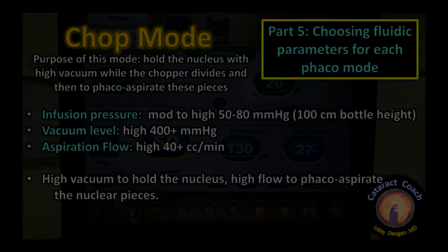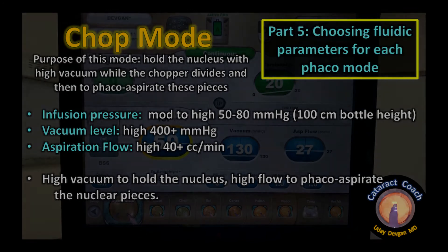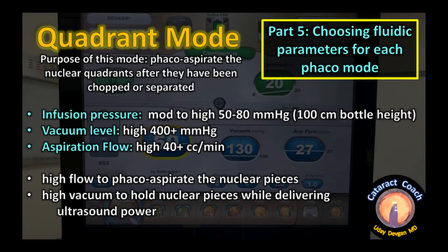Chop mode requires holding the nucleus with high vacuum while the chopper divides, then phacoaspirating the pieces. Infusion pressure must be high to keep up with high aspiration outflow, and vacuum is high to hold the nucleus, with high flow to phacoaspirate the nuclear pieces. Quadrant mode is very similar — phacoaspirating nuclear quadrants after chopping or separation, again requiring high infusion pressure to match high aspiration outflow, high vacuum to hold pieces, and high flow to aspirate them.